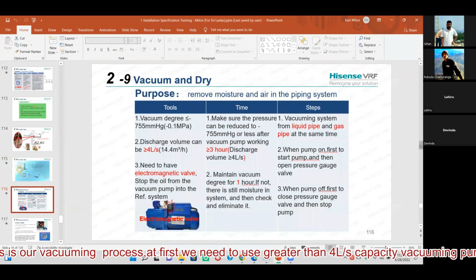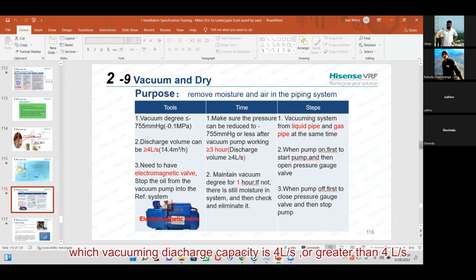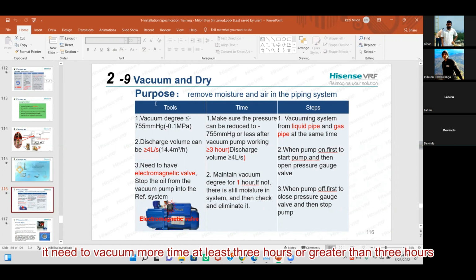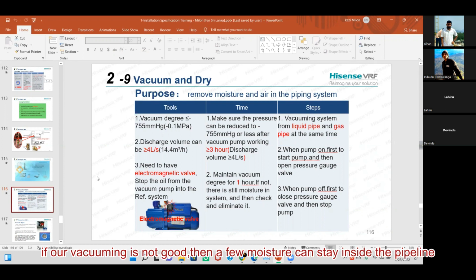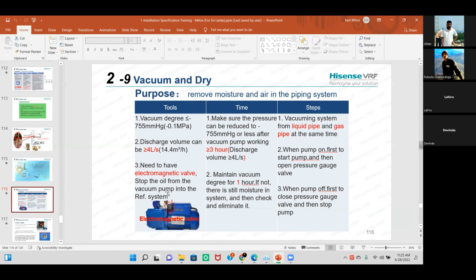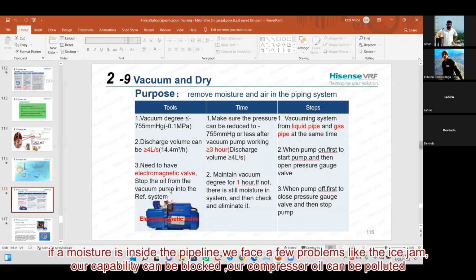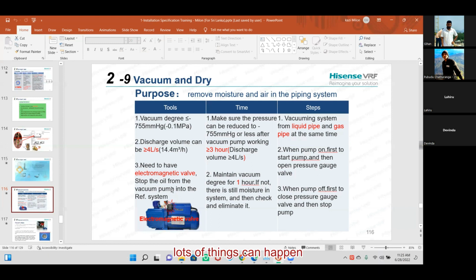This is our vacuum process. At first, we need to use a vacuum pump with discharge capacity greater than or equal to 4 liters per second, and we need to vacuum for a long time, at least 3 hours or more. If vacuuming is not good, then some moisture can stay inside the pipeline. If moisture is inside the pipeline, we face problems like ice jam. Our capillary tube can be blocked. Our compressor oil can be polluted. Lots of things can happen.